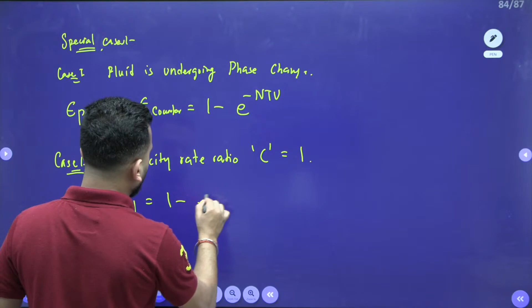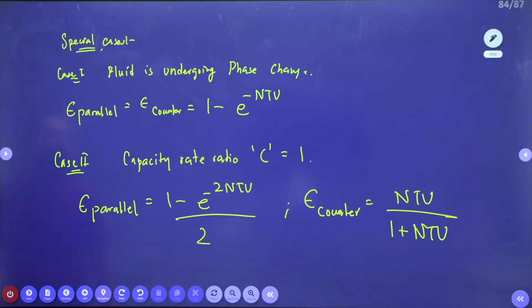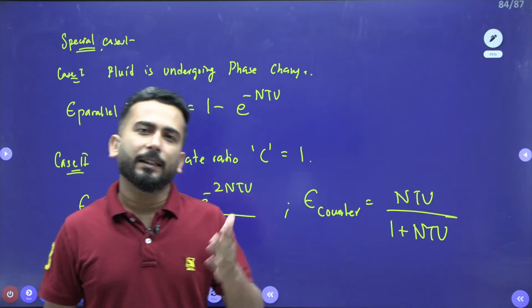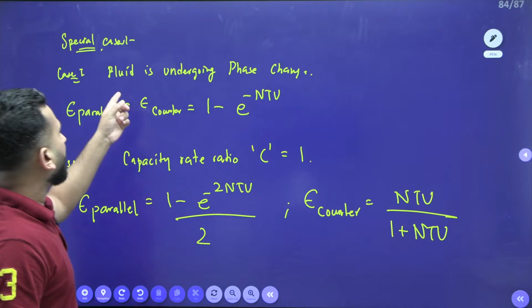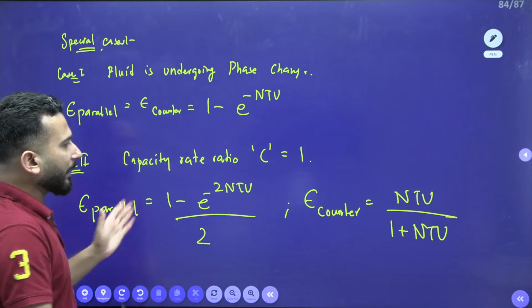So in this case, effectiveness for parallel becomes (1 minus e raised to minus 2 NTU) by 2, and for counter flow, it is NTU by 1 plus NTU. See, in the case of LMTD also, whenever there was a phase change, the LMTD of parallel and counter was the same. Here also, whenever there is a phase change, effectiveness of parallel and counter is coming out the same, which is 1 minus e to the power minus NTU. Fine, no issues.